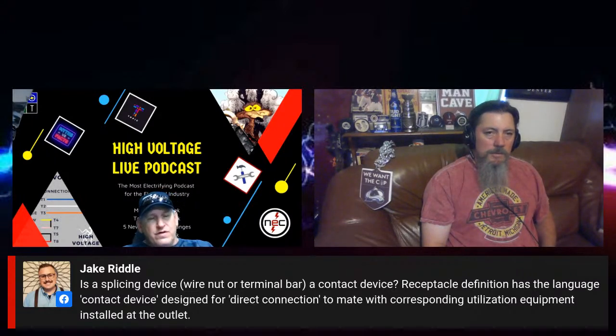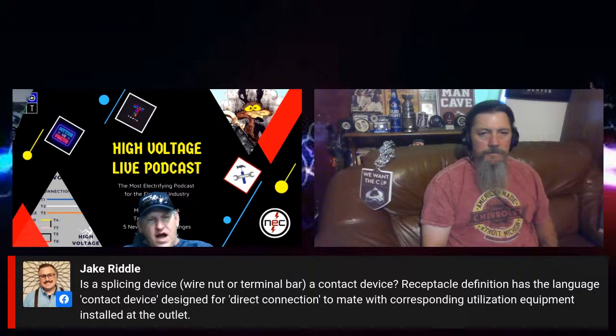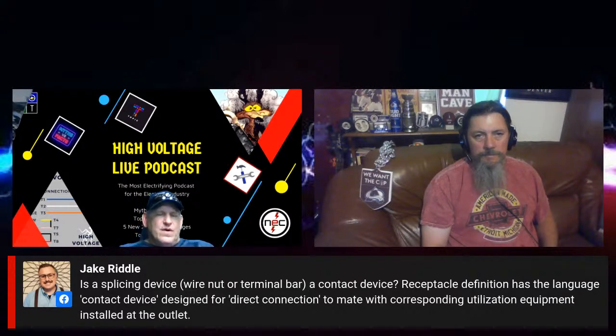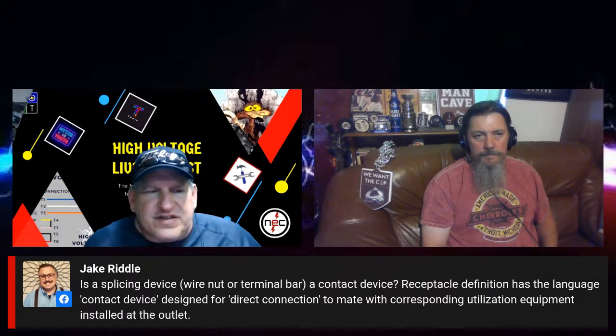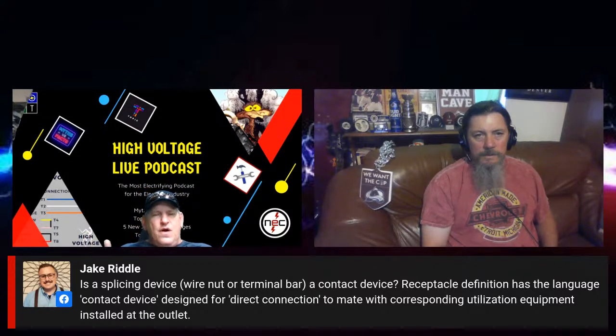So then when you go look at the definition of receptacle, the second sentence is what gets into it, and it talks about a contact device designed for direct connection to mate with corresponding utilization equipment. Now what that's getting into is he was saying, if I go make contact with a device like a receptacle, that's where I'm going to cord and plug something in, and that's where the receptacle is installed at the box, which is the receptacle outlet. And that's why we got two different definitions there for receptacle and receptacle outlet.